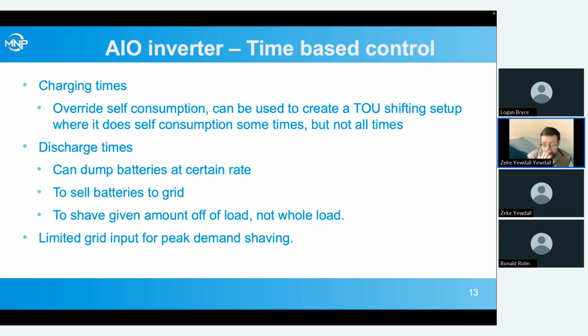Discharge times are to dump the batteries at a certain rate. So you might think, well, wouldn't I do my time of use setup by setting a discharge time from 4 to 8 p.m.? And you could, if you know that you can't meet your whole load and you only want to meet a certain portion. Say you know you've got a 12 kilowatt load during that time, and you want to take 6 kilowatts of it off and leave the rest. You could set a discharge time.